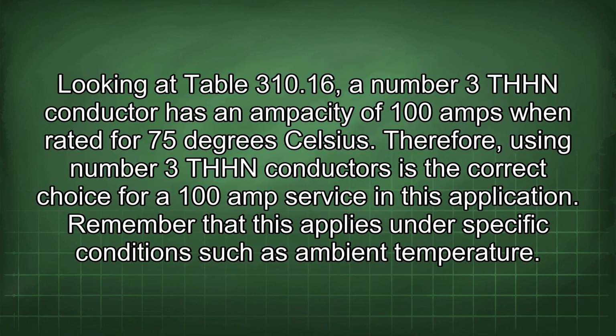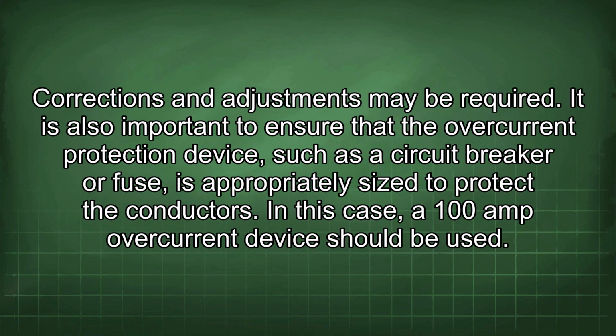Looking at Table 310.16, a number 3 THHN conductor has an ampacity of 100 amps when rated for 75 degrees Celsius. Therefore, using number 3 THHN conductors is the correct choice for a 100 amp service in this application. Remember that this applies under specific conditions such as ambient temperature. Corrections and adjustments may be required. It is also important to ensure that the overcurrent protection device, such as a circuit breaker or fuse, is appropriately sized to protect the conductors. In this case, a 100 amp overcurrent device should be used.